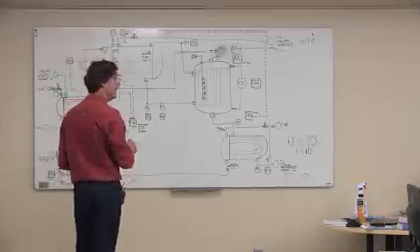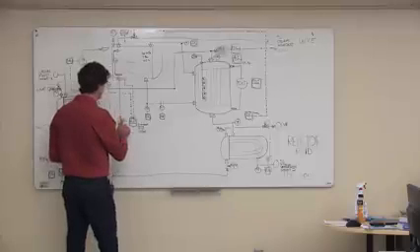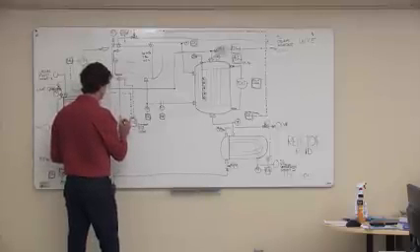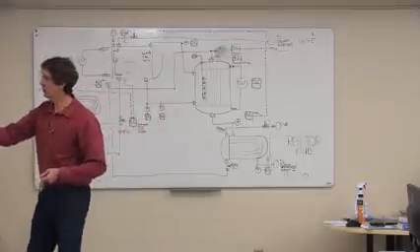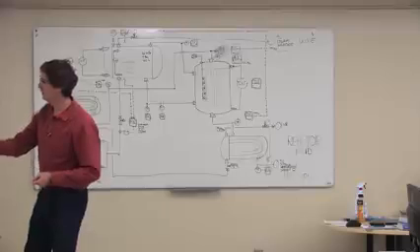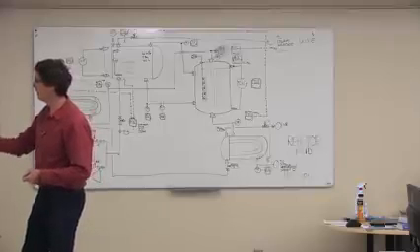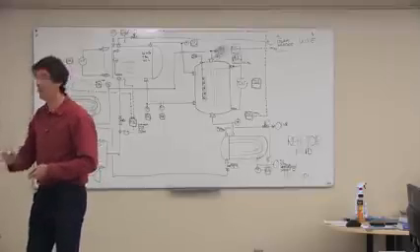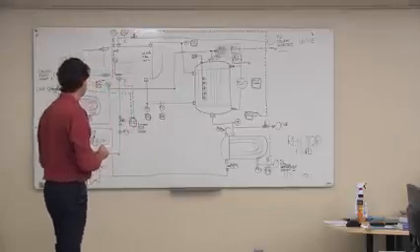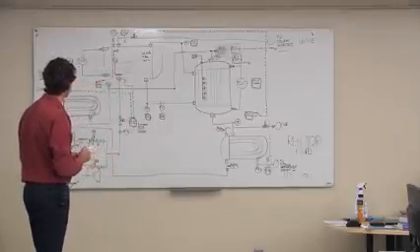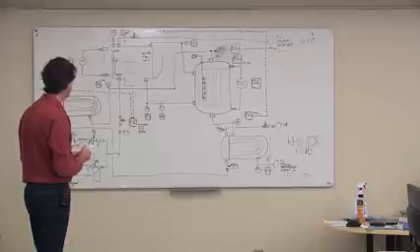What you could do, actually, here's something you probably haven't heard of: fail in last position. Fail in last position looks like this. That makes the control valve a lot more expensive. It's tricky to do that, but that might be the way to solve that.